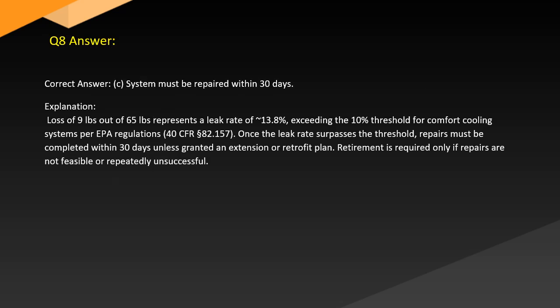Answer. Correct answer: C. System must be repaired within 30 days. Explanation. Loss of 9 pounds out of 65 pounds represents a leak rate of 13.8%, exceeding the 10% threshold for comfort cooling systems per EPA regulations. 40 CFR 82.157. Once the leak rate surpasses the threshold, repairs must be completed within 30 days unless granted an extension or retrofit plan. Retirement is required only if repairs are not feasible or repeatedly unsuccessful.